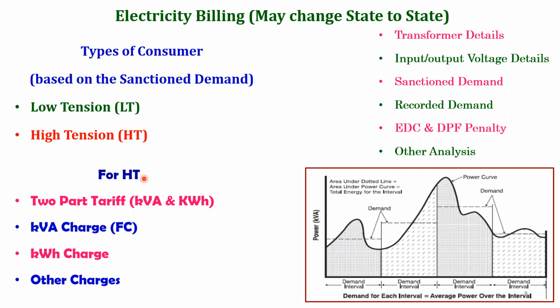So in HT industries, again, the electrical billing is going to be different. It's going to be a KVA billing as well as kWh billing, but only in Tamil Nadu. I know in Maharashtra you already went for kVAh billing. So therefore, you should maintain the power factor near to unity, so that it will be very beneficial for the industry to maintain the total bill at a very close to the satisfactory level.